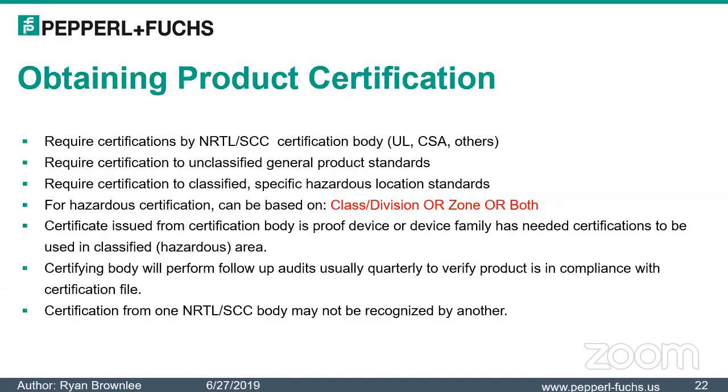We took our box and went to get it tested, and there's a 4-times safety factor, so we have built-up walls to make the box strong. You don't have to test these boxes 100%, because there's a 4-times safety factor. They randomly grab one and say, hey, this one's good, so they must all be good. In the IECEx world, it's 100% tested, so every box gets a check, to make sure it has integrity. And we were even drilling and tapping boxes and testing enclosures after we put the glands in. I don't know anybody that does that.